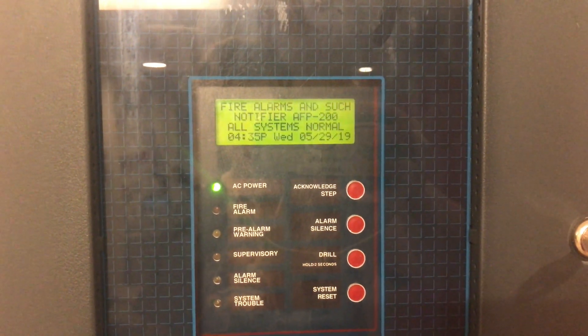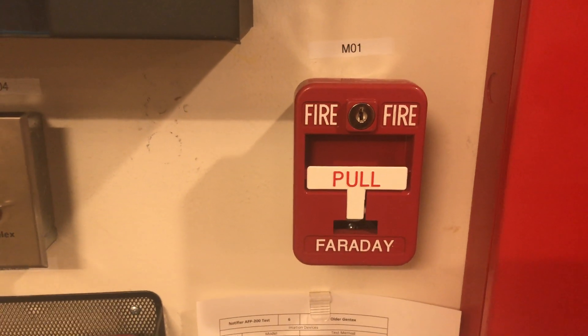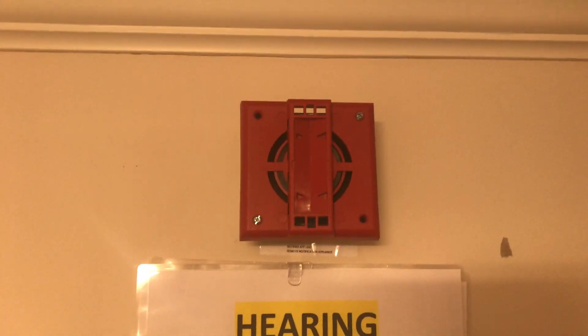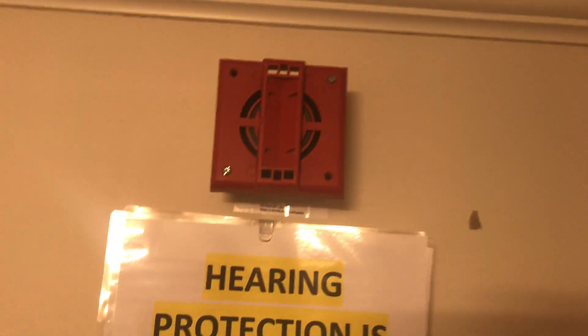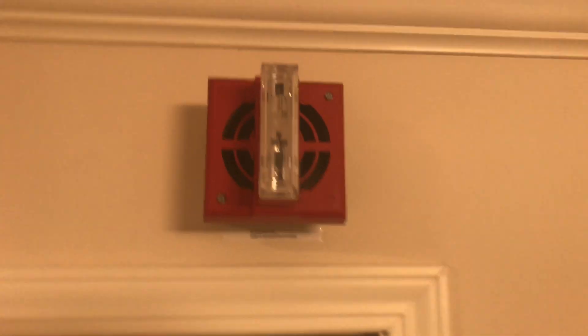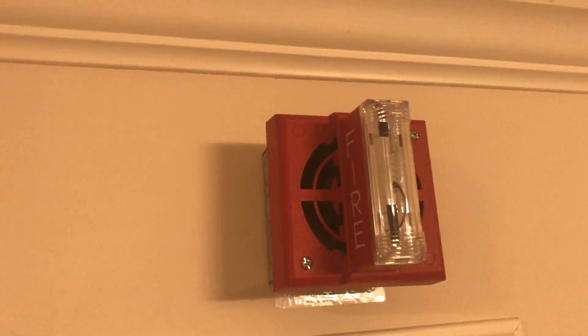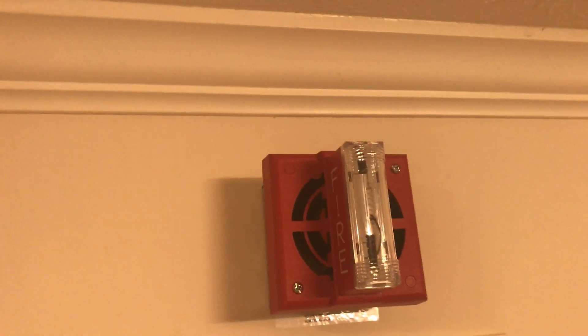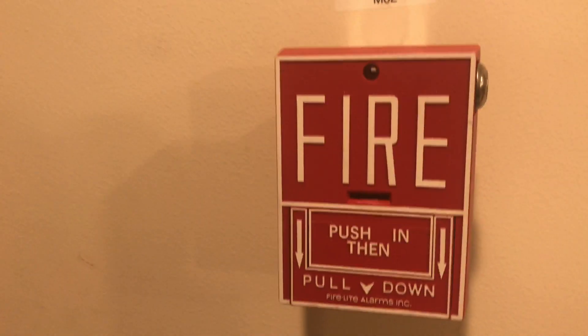Starting down here at the first pull station, we have a Faraday 32 SK2 single-action pull-down key-locking pull station. Going up, we have the Gentex SAG with the strobe removed because it had a dead strobe — this will be doing Code 3 mechanical horn. Over here is a Gentex SHG flashing at 15/75 candela with white fire lettering on the side, doing high-low tone coded at Code 3 in sync with the other horn.